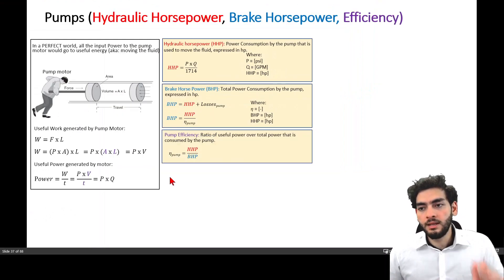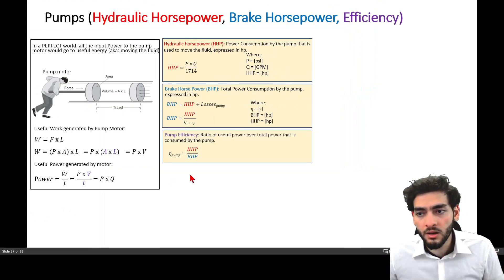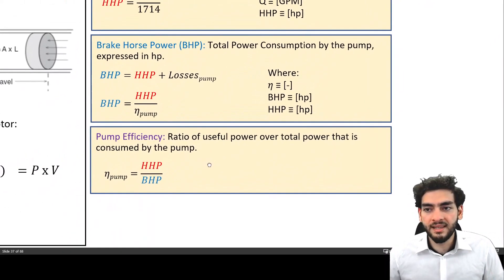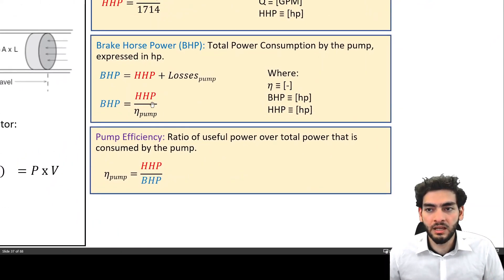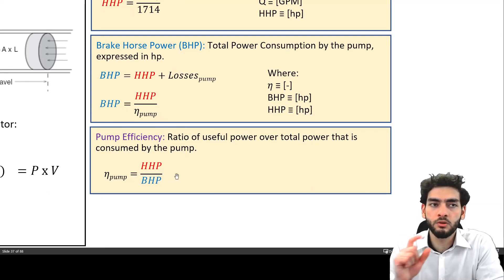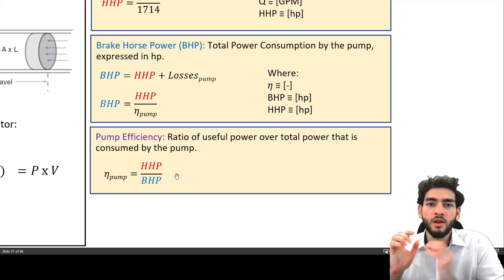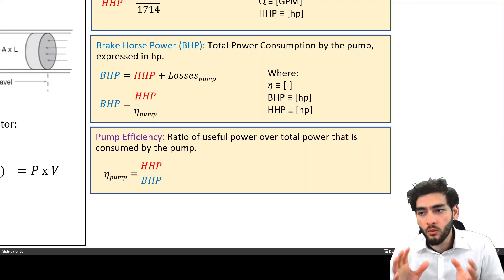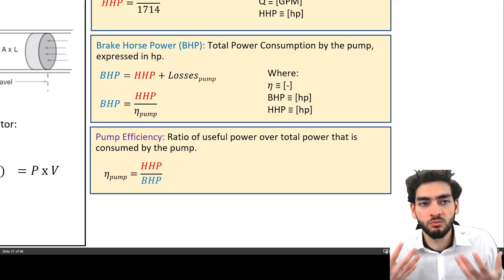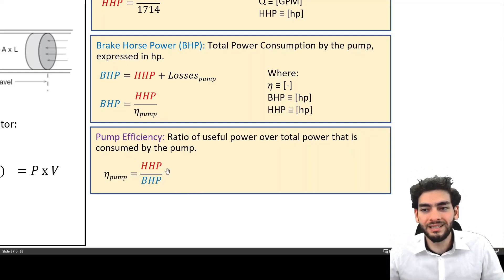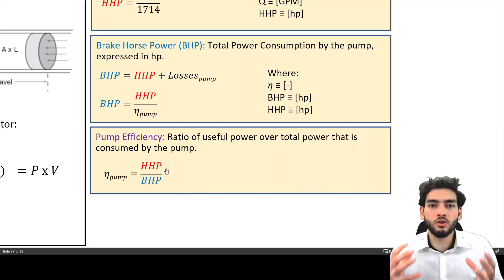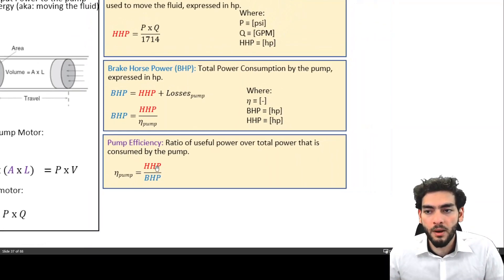The next parameter is pump efficiency, which is what appears in the brake horsepower equation. It is the ratio of useful power over total power consumed by the pump — essentially hydraulic horsepower divided by brake horsepower.